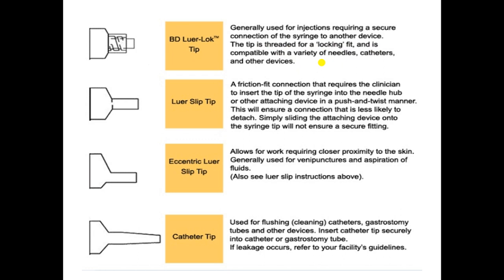The slip tip syringe is very common. The user pushes the needle hub onto the syringe and friction holds the needle hub in place on the syringe tip — there is no locking function like that found on the luer lock. The eccentric tip is used when you need to administer medication parallel to the skin, such as injecting into a surface vein without the needle penetrating too deeply.